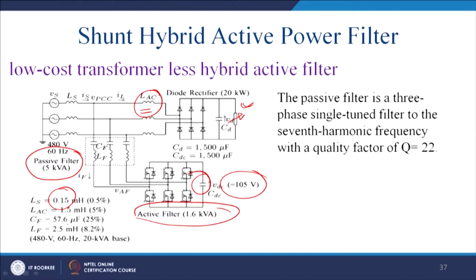And thereafter you have a CF, that value depends on the 60 hertz supply, and it has been tuned to maybe the 7th harmonic, and LF value is 2.5. These combinations will be essentially removing some amount of the 5th or 7th harmonic, and you cannot have a very sharp Q factor here. Here the Q factor of this filter required is maintained at 22. So, that some portion of the 5th harmonic also gets eliminated. Also there is a requirement to have a real power exchange, and you should not offer very high impedance for it. And considering that, the Q factor has to be optimally designed.